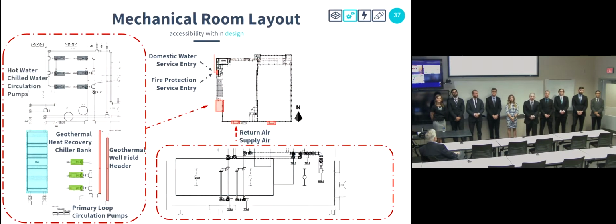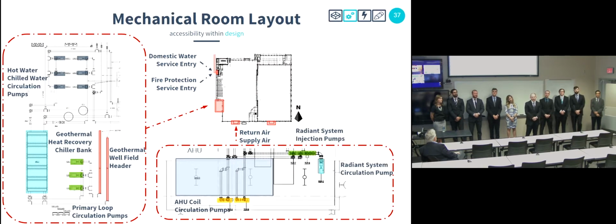By being able to move the west wall, by extending the west wall, we were able to move the domestic water and fire suppression entries from the east side of the building to the west side. The main mechanical room is located in the southwest corner. This room houses the major hydronic equipment, including the geothermal heat recovery chiller bank, the primary and secondary circulation pumps, and the geothermal well field header. The AHU units are housed on the south side of the building in the two AHU rooms that were expanded to accommodate these large units. These rooms also accommodate the hot and chilled water circulation pumps and the hot and chilled water injection pumps and the radiant flooring circulation pumps.